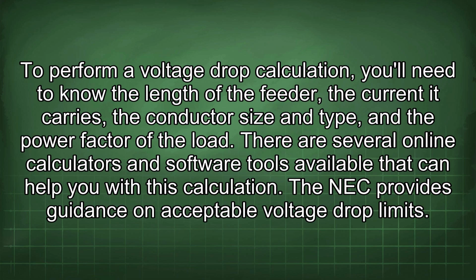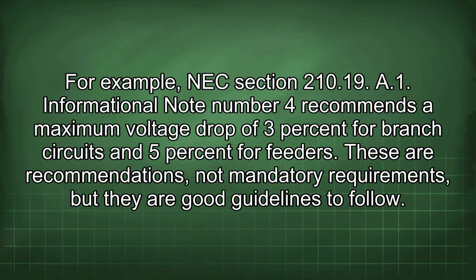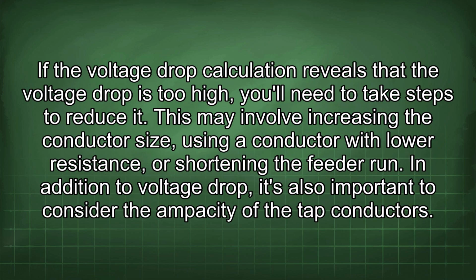The NEC provides guidance on acceptable voltage drop limits. For example, NEC Section 210.19(A)(1), Informational Note Number 4 recommends a maximum voltage drop of 3% for branch circuits and 5% for feeders. These are recommendations, not mandatory requirements, but they are good guidelines to follow. If the voltage drop calculation reveals that the voltage drop is too high, you'll need to take steps to reduce it. This may involve increasing the conductor size, using a conductor with lower resistance, or shortening the feeder run.